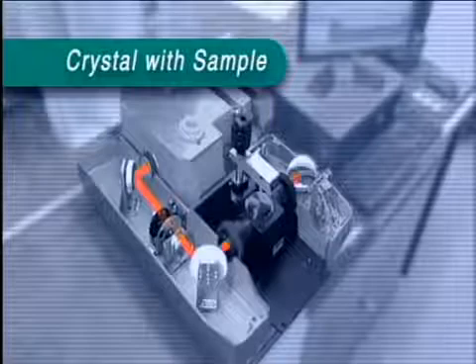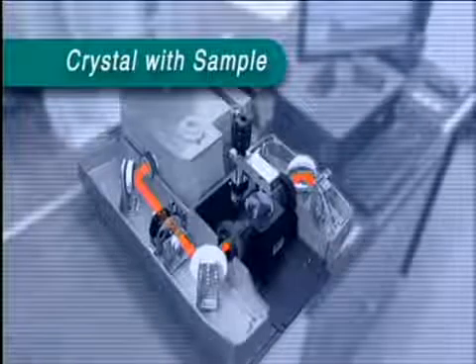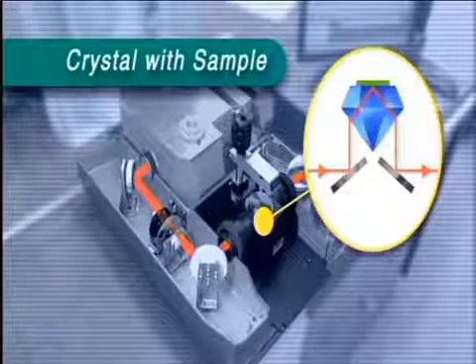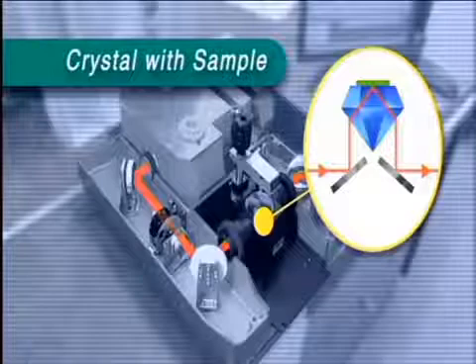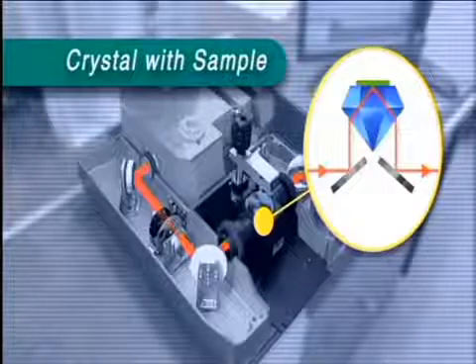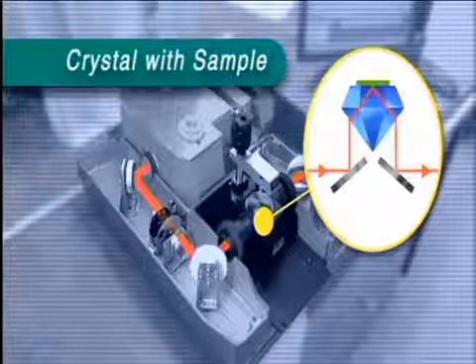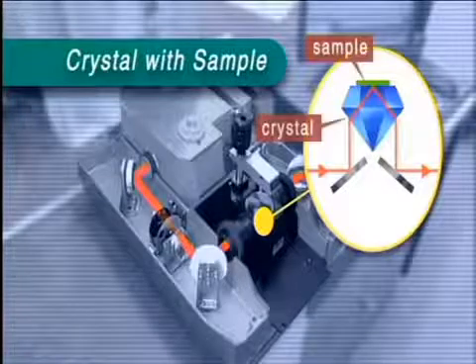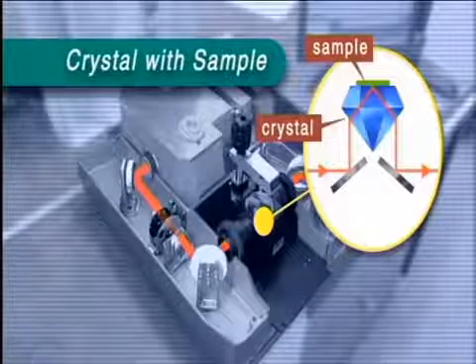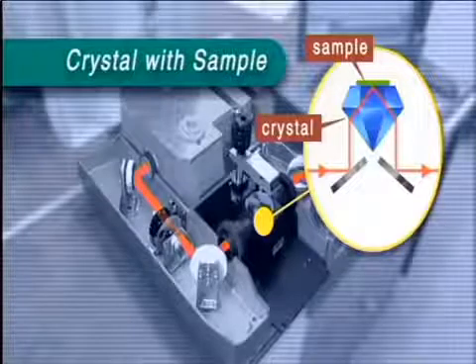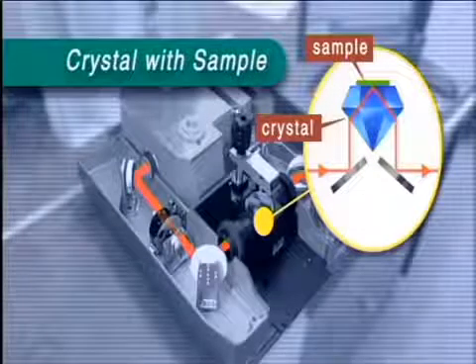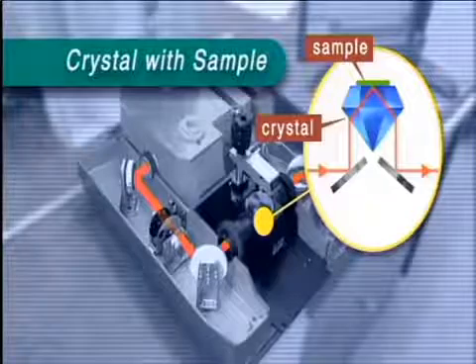This is the sample holder. The sample is placed here on a crystal which is made of diamond or germanium. The IR beam is directed into the sample by a mirror. It is reflected back from the upper surface of the sample, before being guided into the detector by a second mirror. This method is called attenuated total reflection, or ATR.